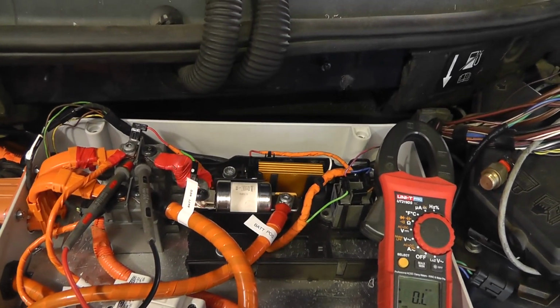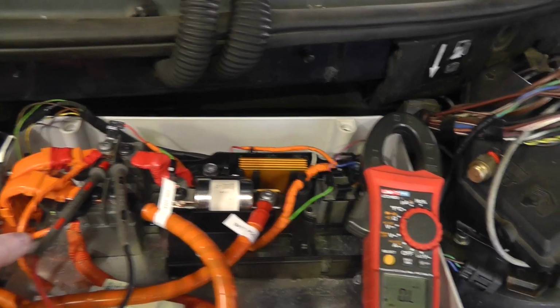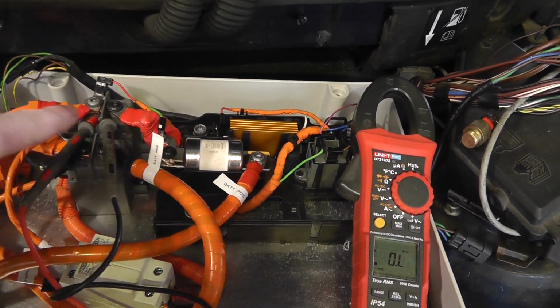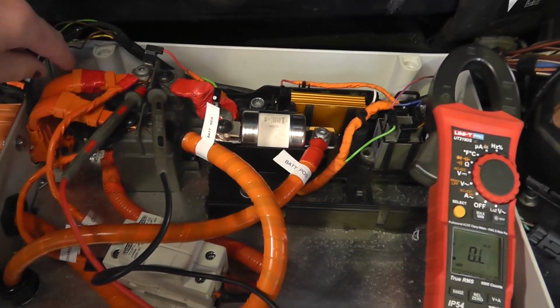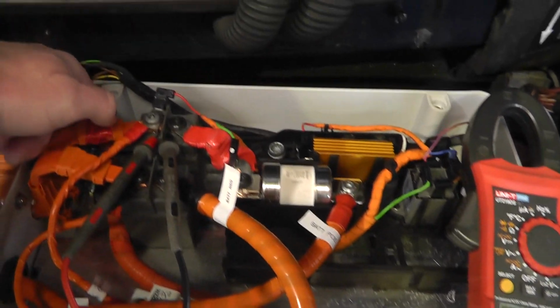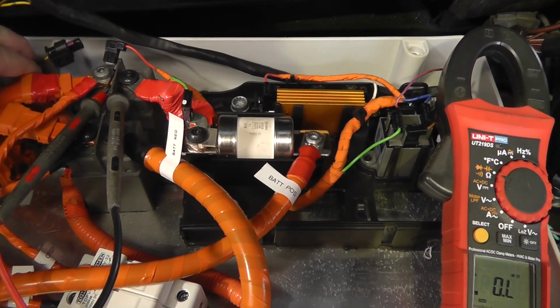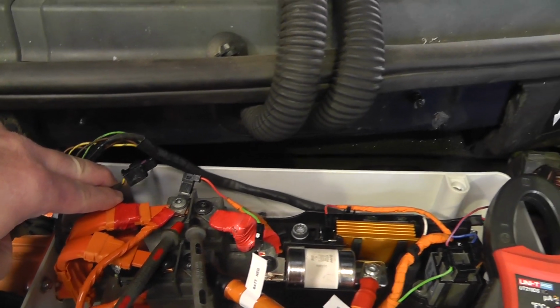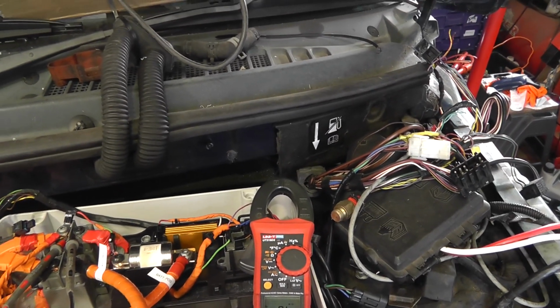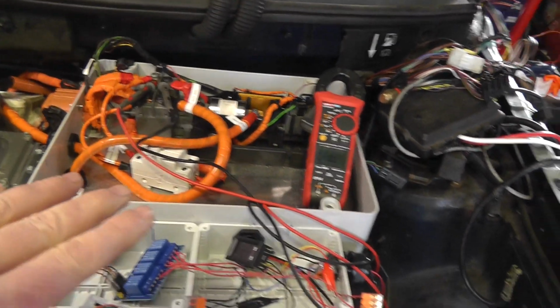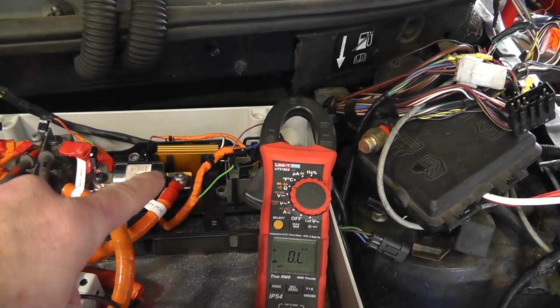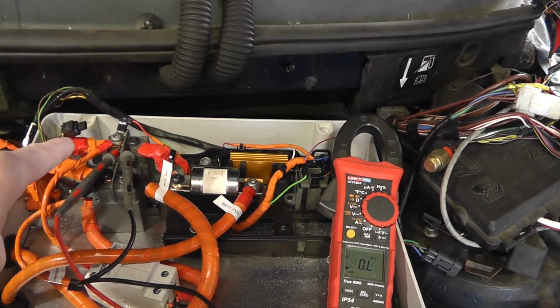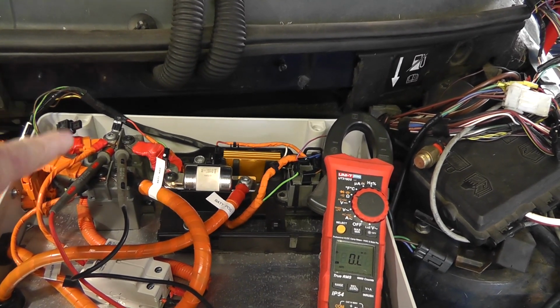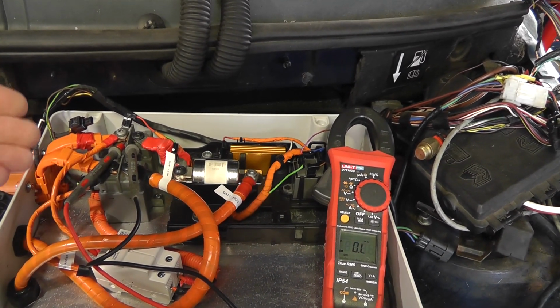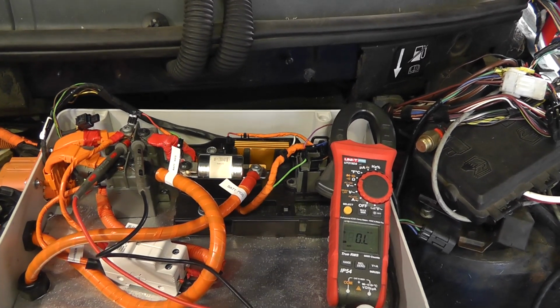What I have at the moment is the multimeter sitting on ohms range and sitting across the main contactor. Now at this point in time, this contactor is not connected, and the reason for that is I want to see, in this first test, the resistor going across that contactor initially, and then after about 5 or 6 seconds, turning off.